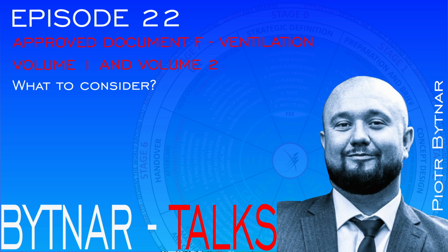Section 1 of that volume deals with ventilation provisions to ensure adequate ventilation while maintaining low noise levels of 30 decibels for sensitive rooms and 45 decibels for other rooms. Extract ventilation is generally required in kitchens, bathrooms, utility rooms and sanitary accommodations. Minimum ventilation rates are specified for different types of rooms and scenarios. Purge ventilation should enable 4 air changes per hour with specific window or door opening requirements. Mechanical and natural ventilation methods are addressed with different requirements based on the building's air tightness.